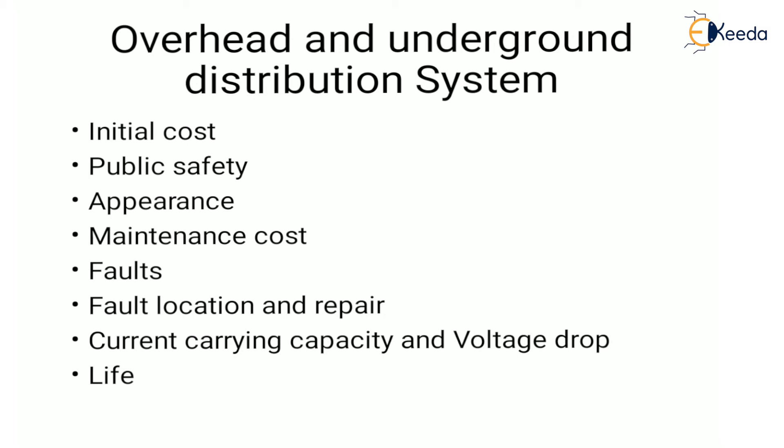Maintenance cost of the underground system is low compared to the overhead system because there are fewer chances of fault and interruption of supply. Regarding faults, underground cables have fewer chances of faults as the cables are laid underground and provided with better insulation. For fault location and repair, if a fault occurs in an underground cable it is very difficult to locate and repair, whereas for the overhead system the conductors are visible and easily accessible.